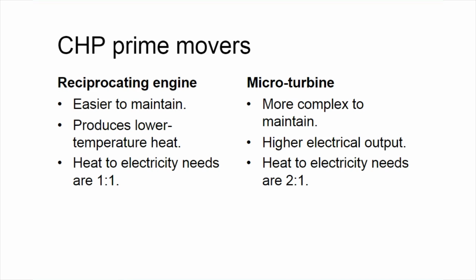Those two types of prime movers, which is the energy generation equipment: the reciprocating engine is pretty easy to maintain, something that most folks are pretty familiar with, but they tend to produce a lower heat, mostly hot water, not steam, and you want to look at the needs of the building and how much electricity you need to offset versus how much heat you can use. Reciprocating engines tend to be more one-to-one heat to electricity, whereas the microturbines or gas turbines produce a higher level output, more steam, higher pressure, which makes them a little more complex to maintain, but you do get more electricity out of them, so you might want to look at those in a situation where you have a lower heat load and need to offset more electricity.